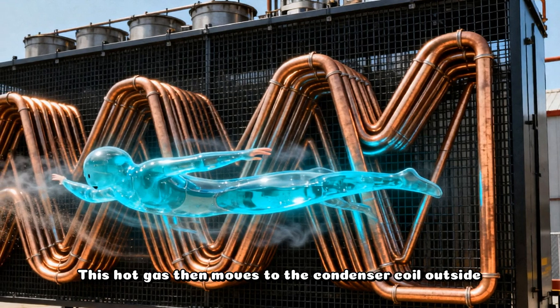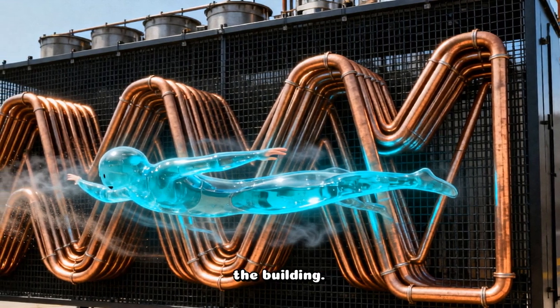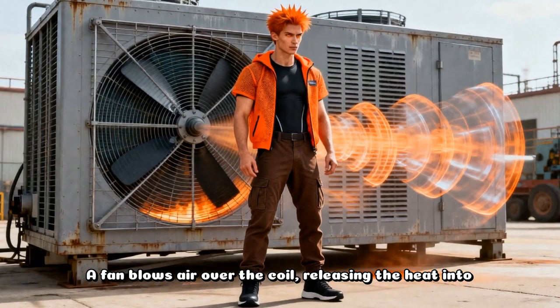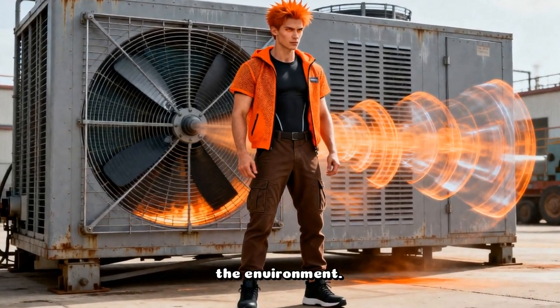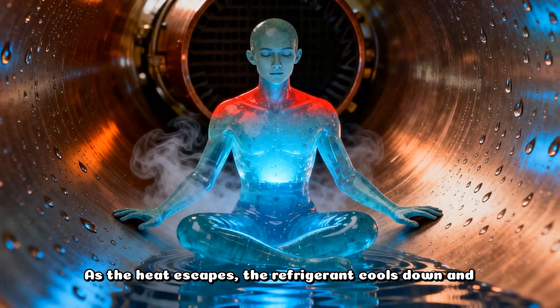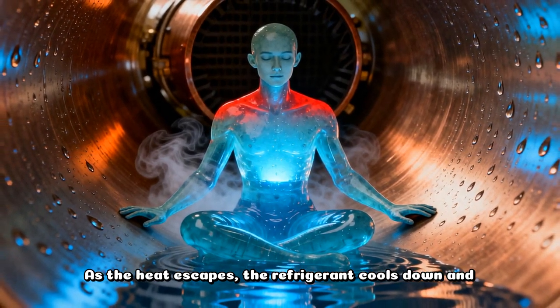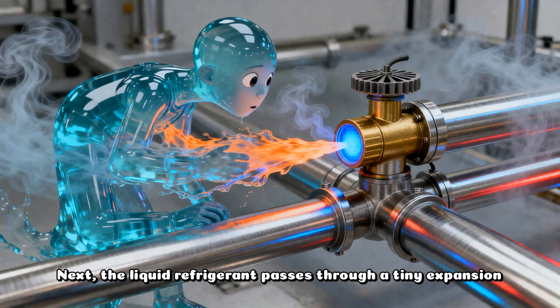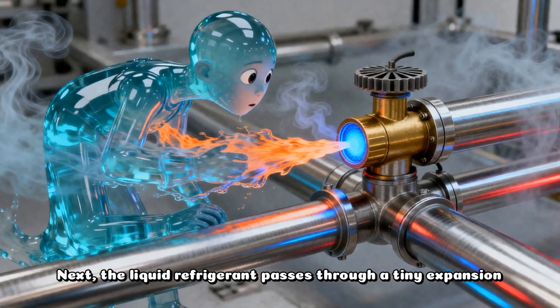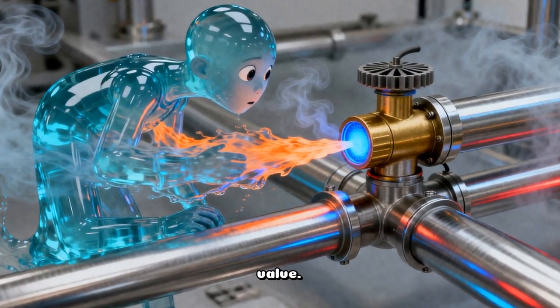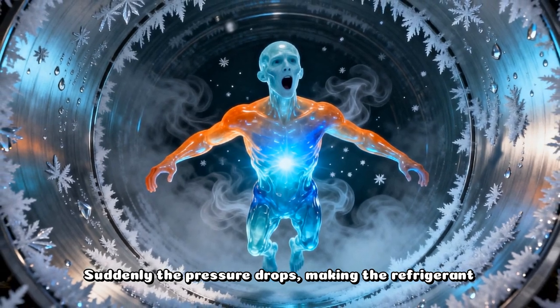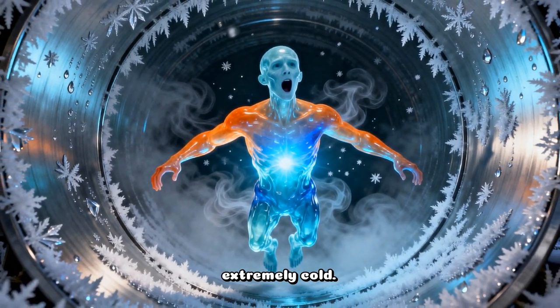This hot gas then moves to the condenser coil outside the building. A fan blows air over the coil, releasing the heat into the environment. As the heat escapes, the refrigerant cools down and turns into liquid. Next, the liquid refrigerant passes through a tiny expansion valve. Suddenly, the pressure drops, making the refrigerant extremely cold.